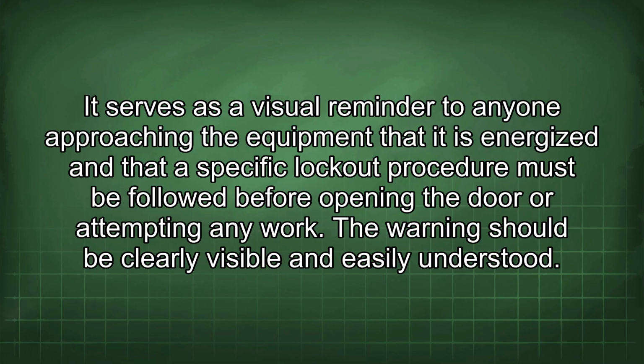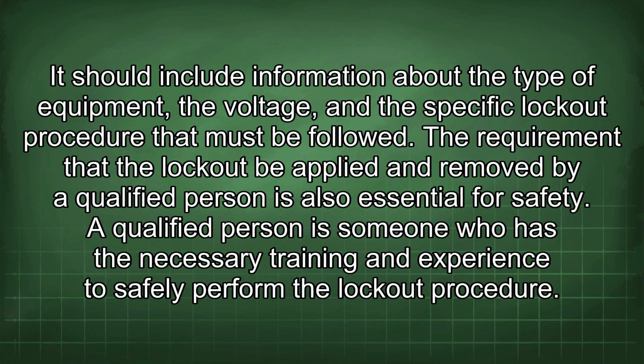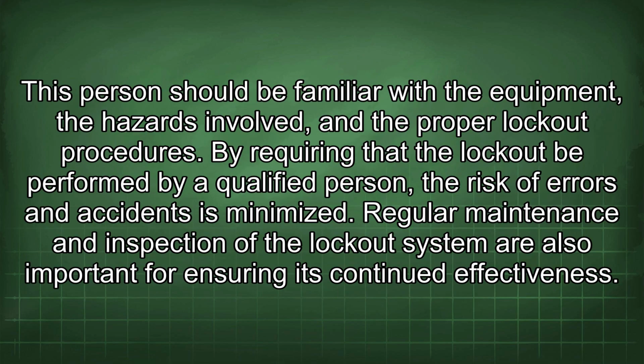The warning should be clearly visible and easily understood. It should include information about the type of equipment, the voltage, and the specific lockout procedure that must be followed. The requirement that the lockout be applied and removed by a qualified person is also essential for safety. A qualified person is someone who has the necessary training and experience to safely perform the lockout procedure. This person should be familiar with the equipment, the hazards involved, and the proper lockout procedures. By requiring that the lockout be performed by a qualified person, the risk of errors and accidents is minimized.